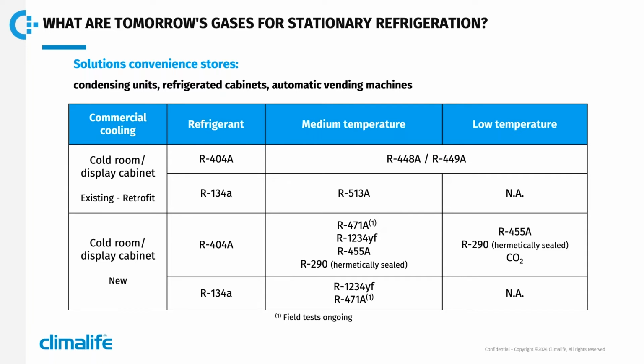On this subject, Emerson estimates that a CO2 installation will cost 30% more than an HFC or HFO solution for shops over 2,500 square meters, and 40% more for shops less than 2,500 square meters, and 50% more for stores under 1,500 square meters. Of course, the environmental aspect must also be taken into account, because do not forget that F-Gas aims to reduce global warming, so the choice of refrigerant should be based on the most energy efficient solutions to avoid a negative carbon impact in the long term.